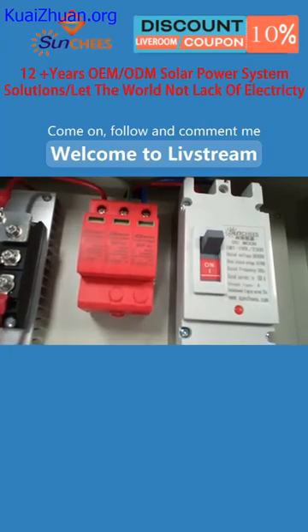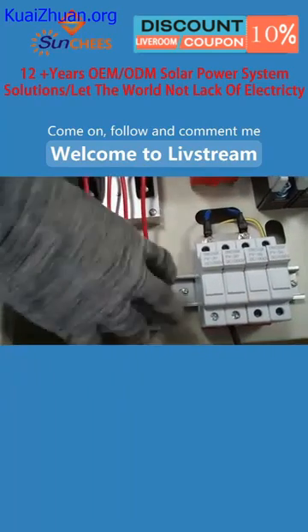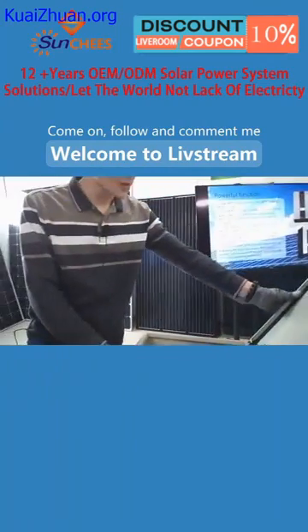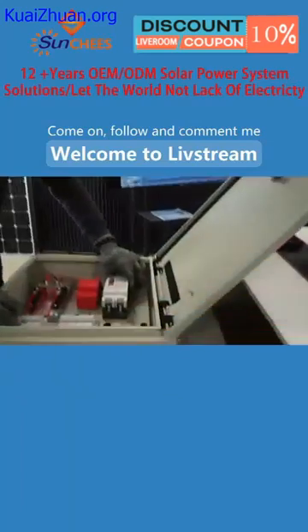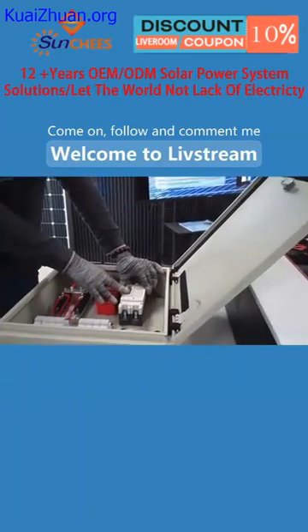And this PV combiner is 4 ways in. That means it can connect at least 4 strings of PV arrays. And one more thing is that for the PV combiner, we are using the DC breaker to protect the system, because the power from the PV array is direct current power, so the breaker needs to be a DC breaker. For this one, the rated voltage is DC 500 volt, and the rated current is 100 amp. It is much more than enough to protect a 6 kilowatt solar power system.